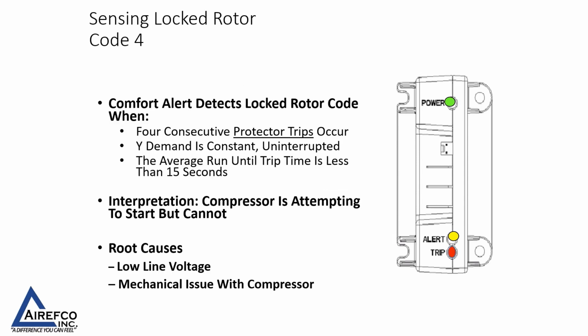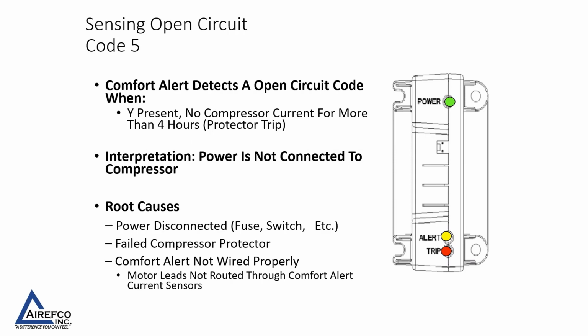If the amber LED is flashing 4 times, this means that it has sensed a locked rotor on the compressor. 4 consecutive protector trips have occurred. The compressor is attempting to start, but cannot. And then it gives you some root causes of what to check with the compressor. A flashing 5 on the amber LED detects an open circuit code, that Y is present, but there is no compressor current for more than 4 hours. So power is not connected to the compressor. And then it gives you some things to check to find out why.